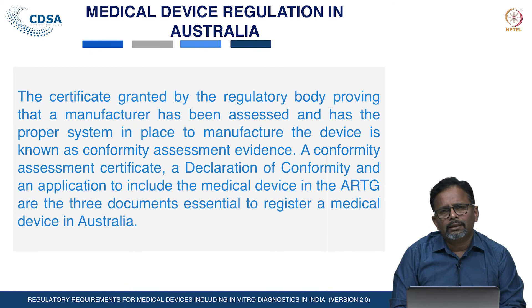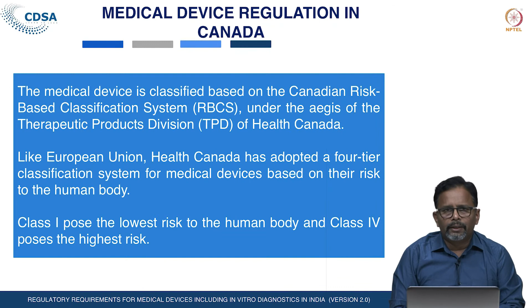In Canada, Health Canada is the nodal agency for regulation of medical devices. Under Health Canada, the therapeutic product divisions are responsible for regulation of medical devices. Also in Canada, medical devices are classified based on risk into class 1, class 2, class 3 and class 4 devices, and class 4 is the highest risk in Health Canada.